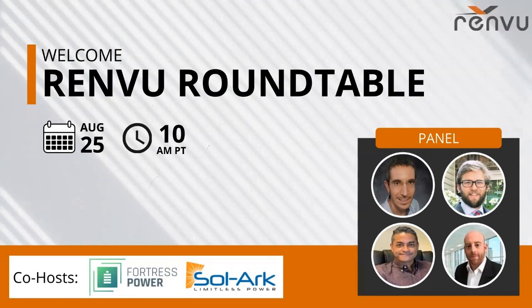Sure, I'll touch on that a little, and Dustin, chime in if I miss anything. If you have an existing grid-tied system, typically, if it's a SolarEdge system with optimizers, the optimizers will already satisfy the rapid shutdown requirement. If it's an Enphase system, the microinverters will already satisfy the rapid shutdown requirement. And I believe SMA also has their own rapid shutdown components. So if you're installing the SolArk system AC coupled to one of those existing systems, rapid shutdown should already be resolved.